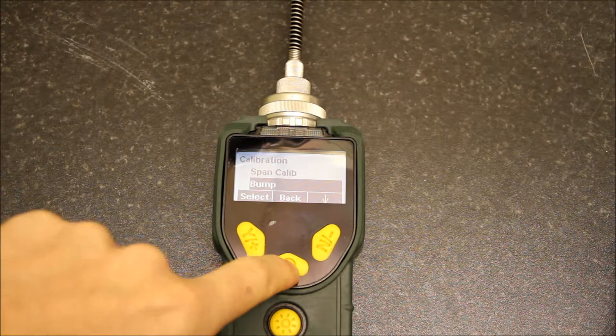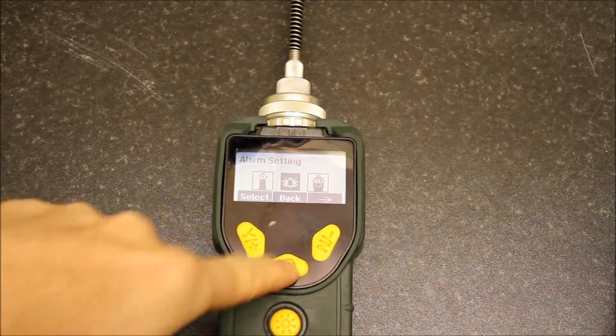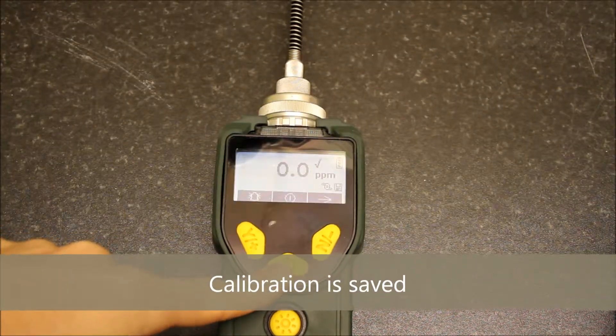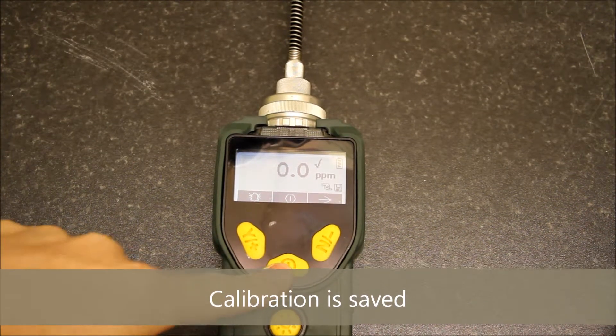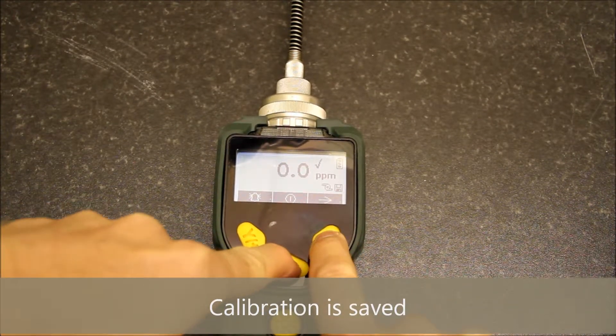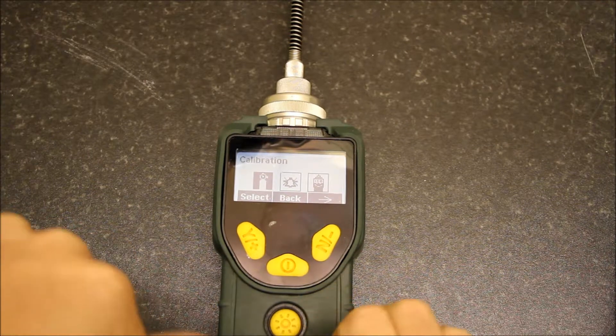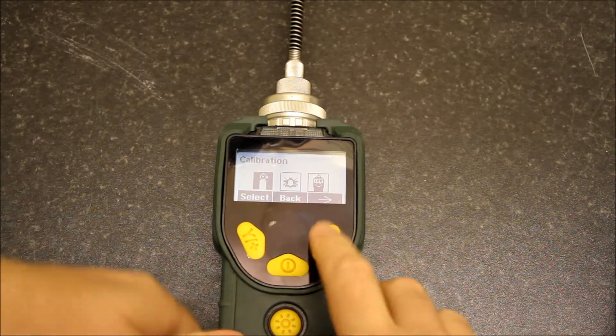If we press back and back again, you will see that will save the calibration. Now if we drop back into that menu, it won't ask for the password a second time because we've already entered it.